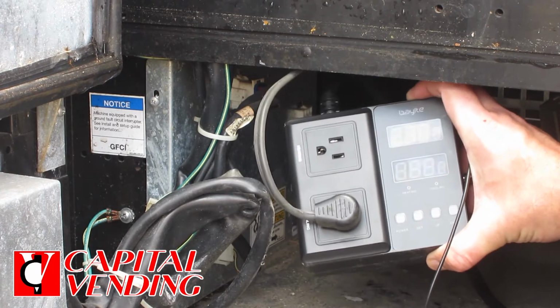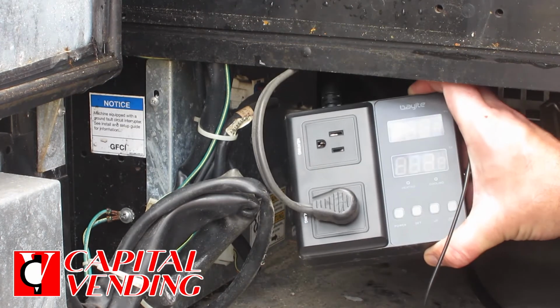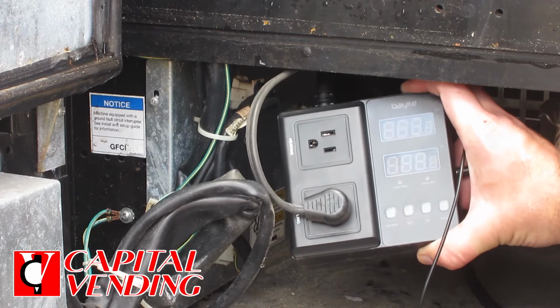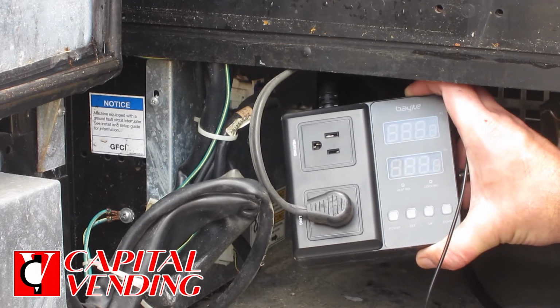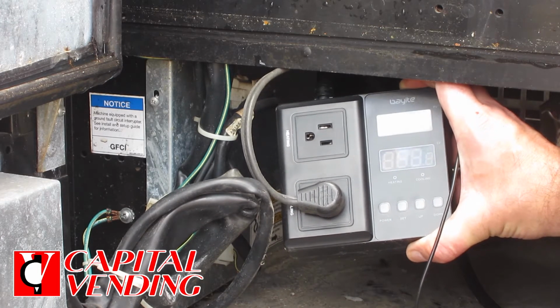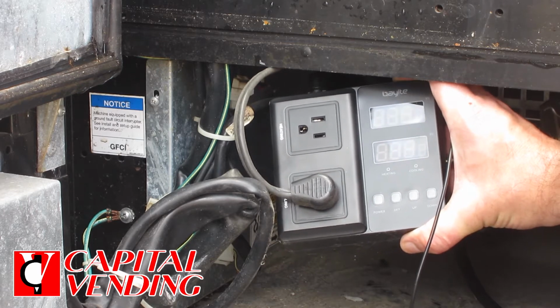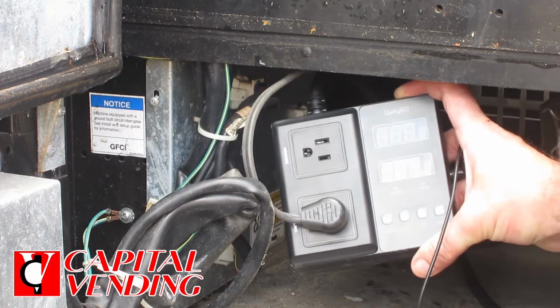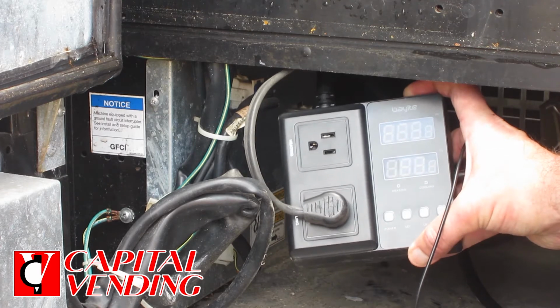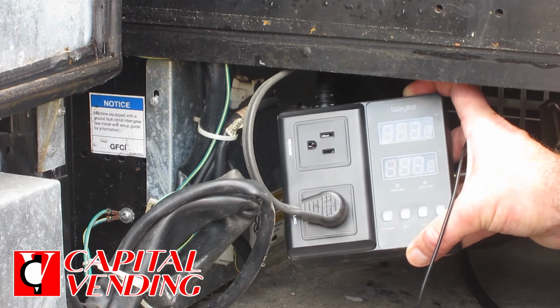We do have some customers that actually use this to control the cooling. In the case of this machine, it's nice if you have a soda vending machine with issues where it's not turning on the refrigeration system. You could have a defective relay, a defective temperature probe, or the part of the control board that controls the refrigeration could be bad.